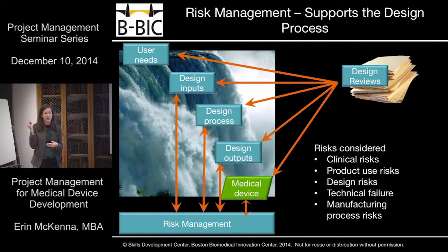Do we see a significant clinical issue that could occur if we have a catheter that needs to be delivered and it's got some kind of a hydrophilic coating on it, and now the product is stuck in the package because humidity got in there? What are the risks that could occur? So you're going to be thinking about those things and using tools like failure modes effects analysis to really analyze and help you determine where you're going to focus the number of tests that you might do for each specification.